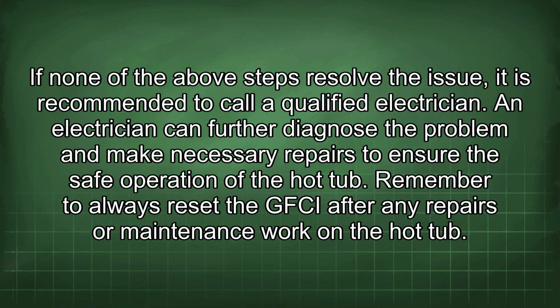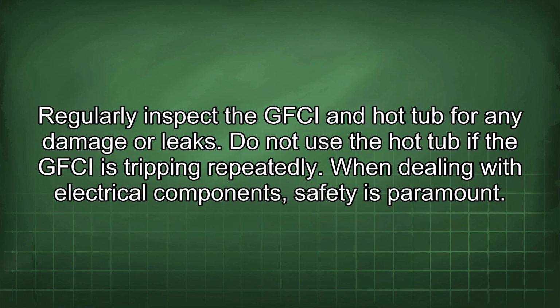If none of the above steps resolve the issue, it is recommended to call a qualified electrician. An electrician can further diagnose the problem and make necessary repairs to ensure the safe operation of the hot tub. Remember to always reset the GFCI after any repairs or maintenance work on the hot tub. Regularly inspect the GFCI and hot tub for any damage or leaks. Do not use the hot tub if the GFCI is tripping repeatedly.